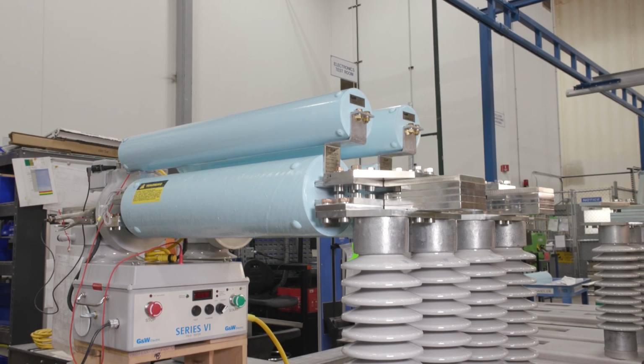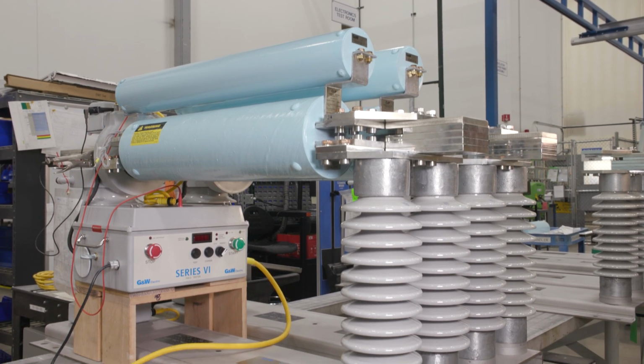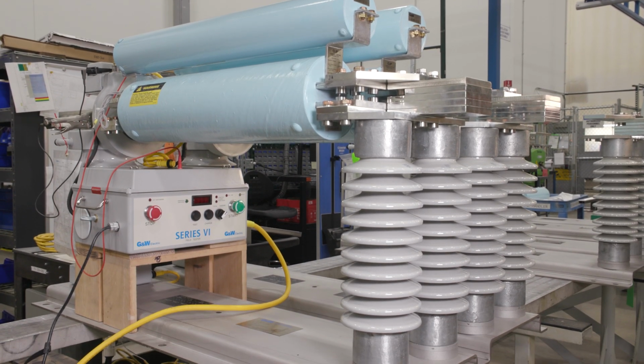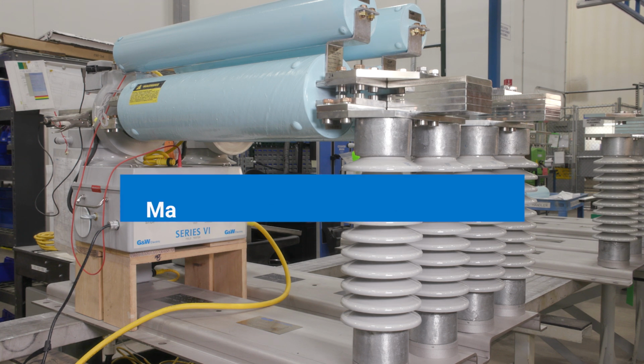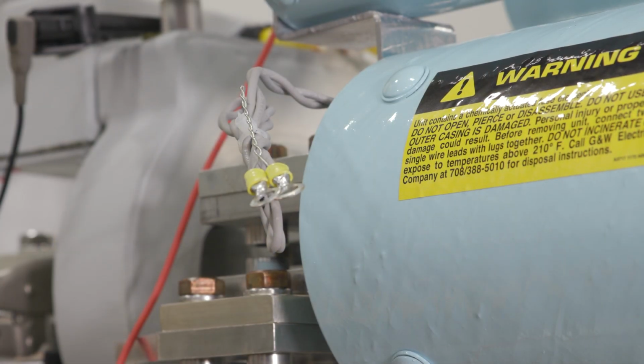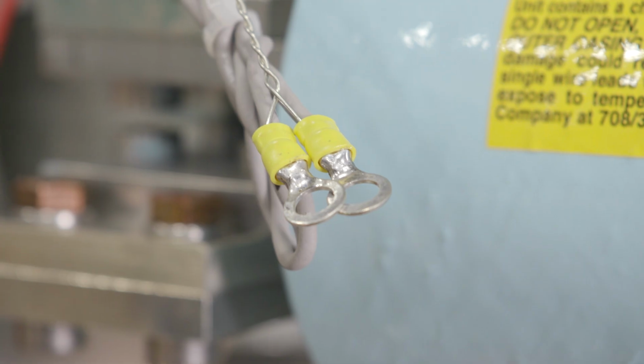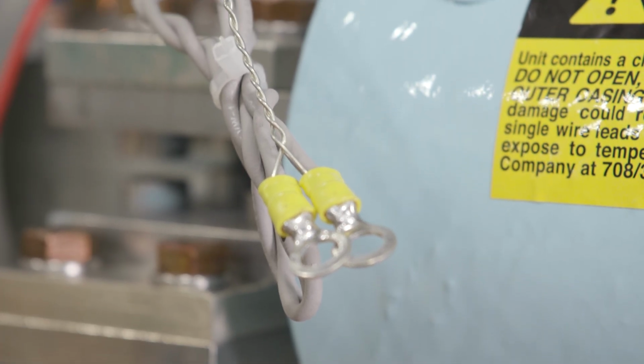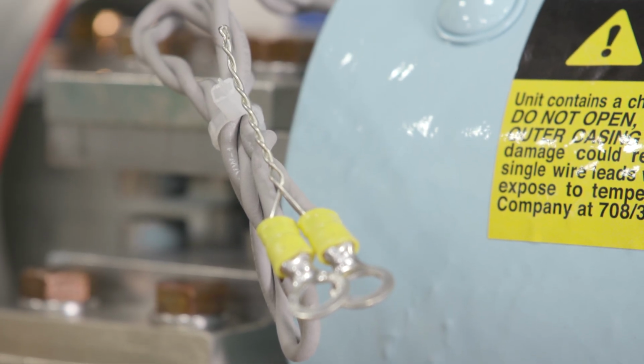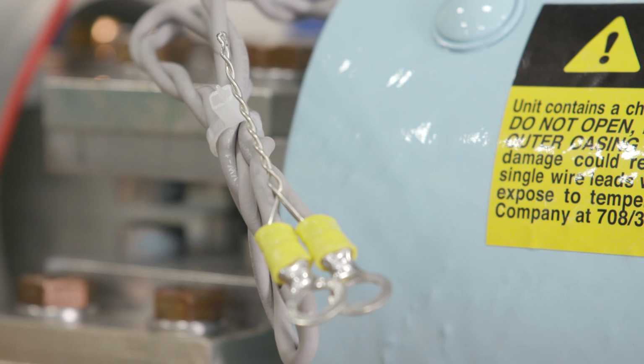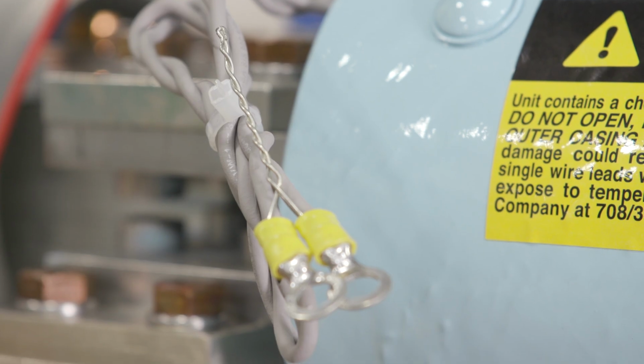De-energize the circuit in which the CLiP current limiting protector is installed, and ground both ends according to local practices. Make certain that the power cannot be backfed into the CLiP current limiting protector circuit. To prevent the unintentional firing of the interrupter, the firing leads must be shorted before they are disconnected. Do not remove the shorting wire until all testing has been completed and the firing leads have been connected to the SFL.